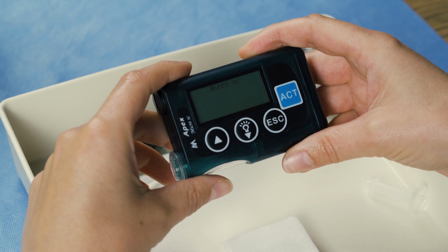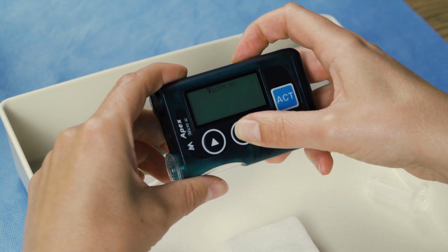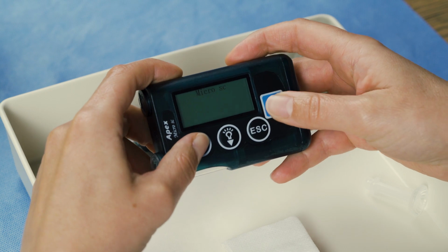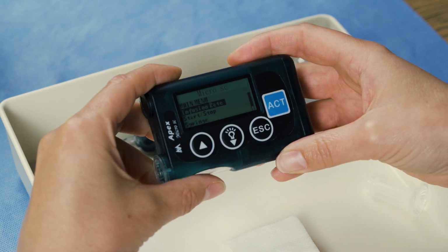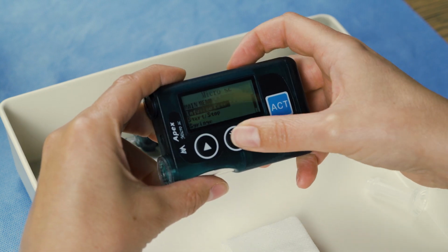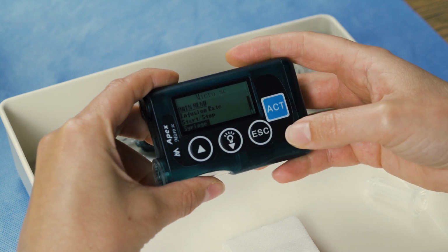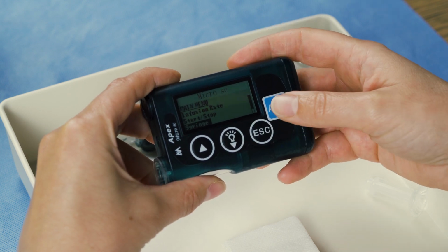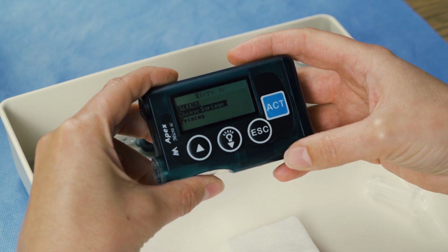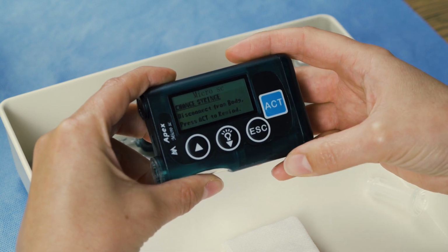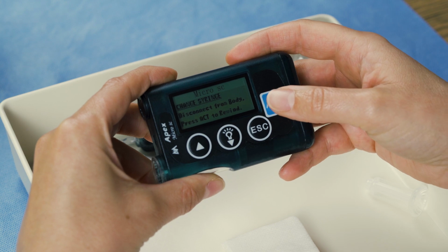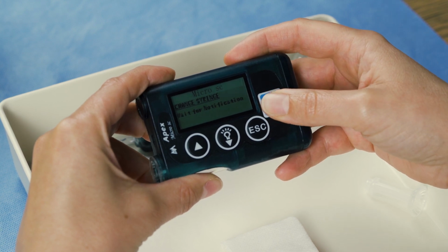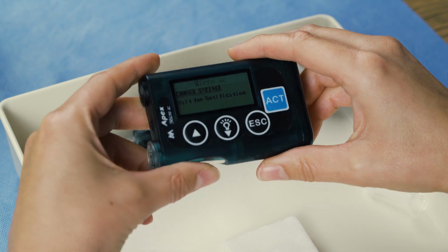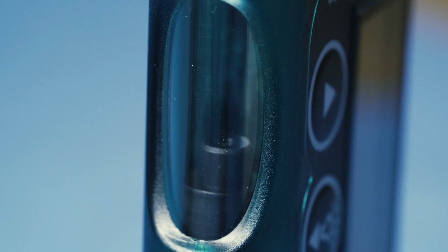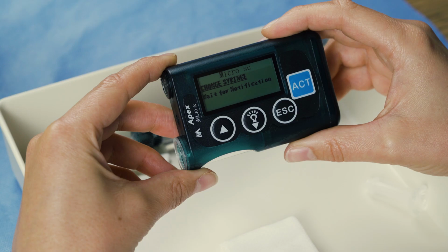Press and hold the light bulb button to light up the screen. Press the up arrow and act buttons to unlock the screen and to display the main menu. Press the down arrow twice to go down to the third option, syringe, and press act to select the first option, change syringe, and act again. The pump menu refers to the drug reservoir as syringe. Press act a third time to rewind the push rod, causing it to retract so it's in the start position. Wait until you hear a beep sound.